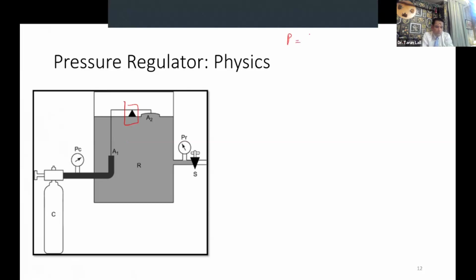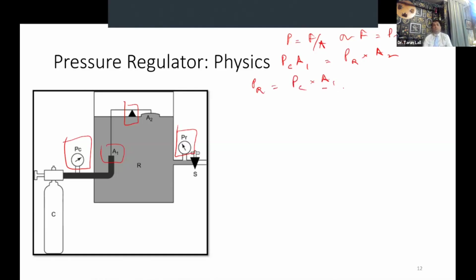So we know that pressure is equal to force upon area, or we can say that force is equal to pressure into area. Now, let the cylinder pressure be PC, what you see here, and the area be A1. So PC into A1 will be equal to the output pressure of the regulator into A2. So a very simple calculation would be that the output pressure of the regulator will be the cylinder pressure into the ratio of A1 to A2. This is what the company has to design. If I know the ratio between A1 and A2, I can decide the output pressure.